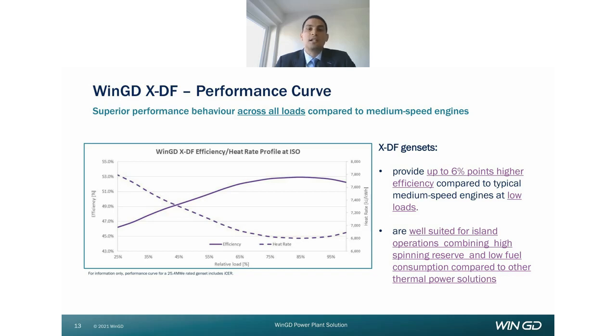Now, I present in these slides our efficiency curve. As you can see, we have a very high efficiency. Actually, our efficiency is the highest among all the open cycle technologies if you compare this curve with a typical medium speed genset and open cycle gas turbines. In particular, if you look at the low loads between 30, 40, 50%, our efficiency is very high. We speak about more than 45% efficiency. This represent up to 6% points higher efficiency compared to a medium speed genset.